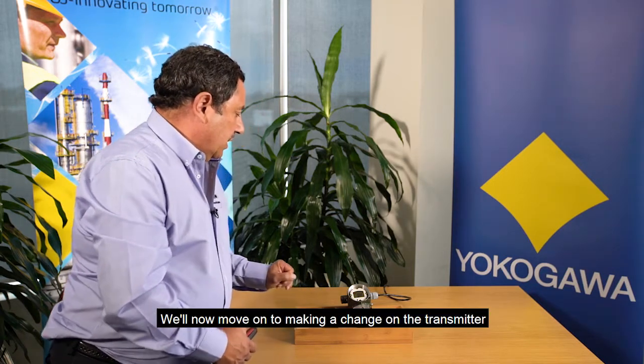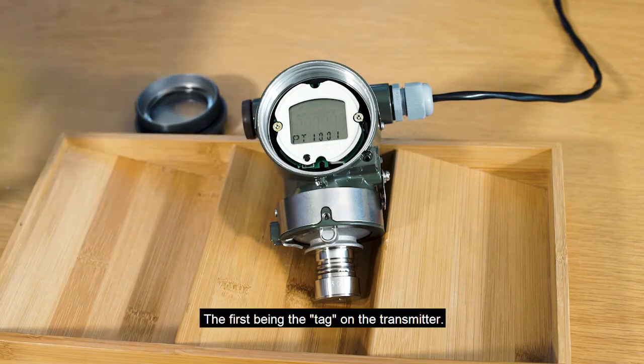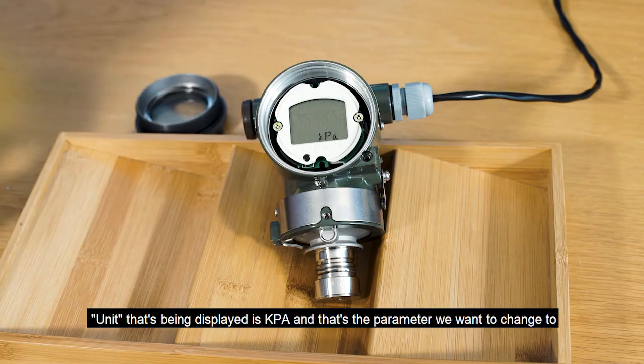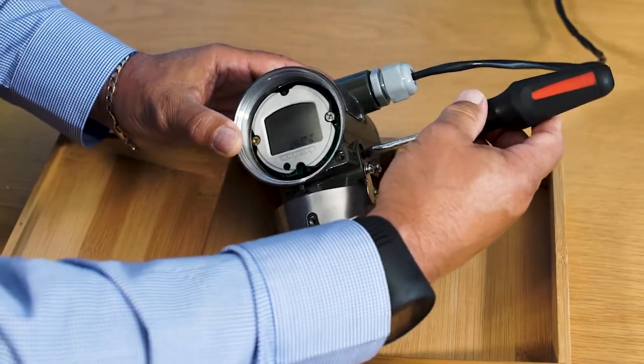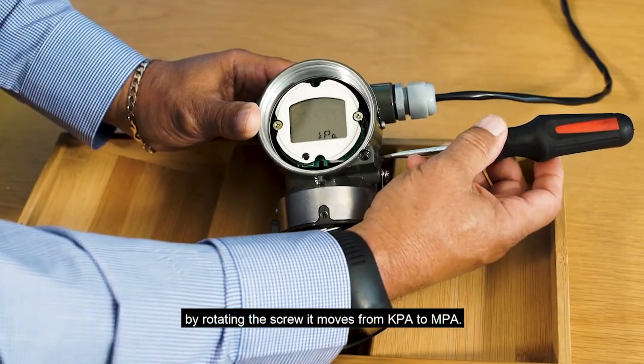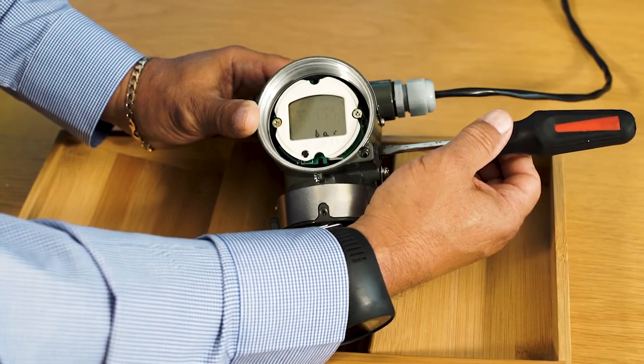We'll now move on to making a change on the transmitter and demonstrate how simple that is. Simply activate LPS — the tag confirms that we're into local parameter setting functionality. The first parameter being the tag on the transmitter. The unit being displayed is kPa and that's the parameter we want to change to bar. So I'll go to the range setting switch, then the zero adjustment switch and turn the screw. By rotating the screw it moves from kPa to MPa to millibar to bar — and that's where we want to be, so we'll leave it at bar.